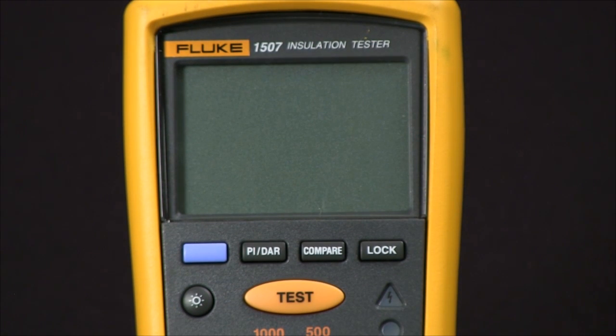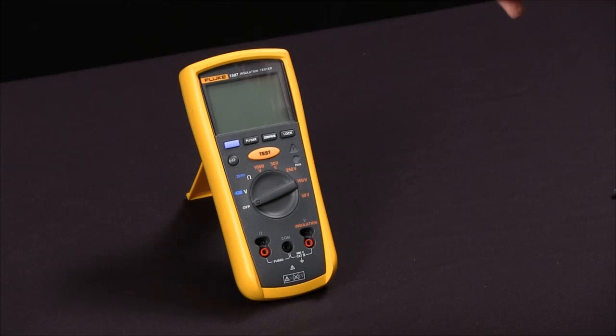Polarization index, which is a 10 minute to 1 minute ratio time test, and dielectric absorption ratio, which is a 1 minute to 30 second test.